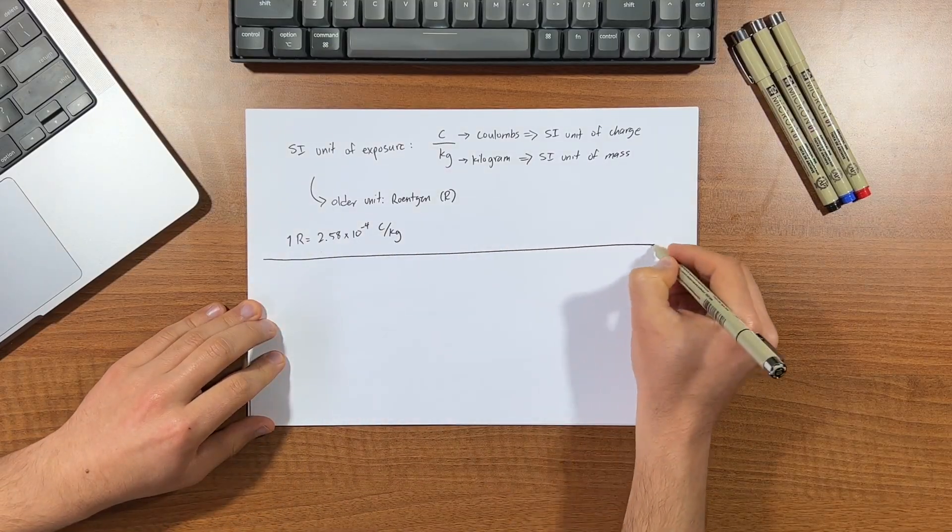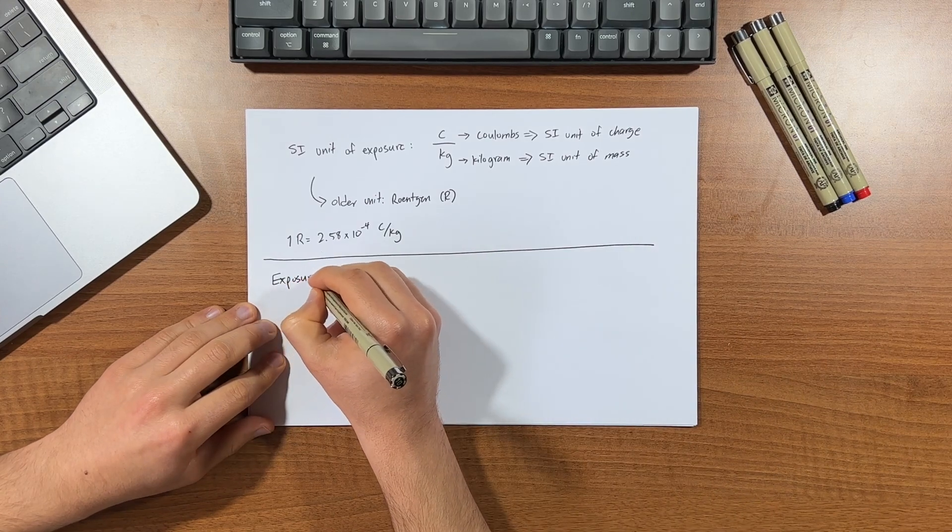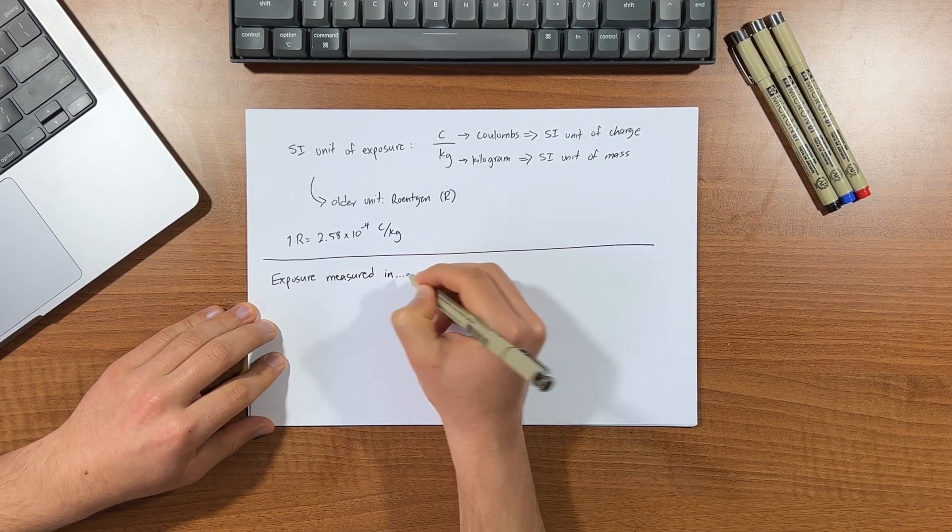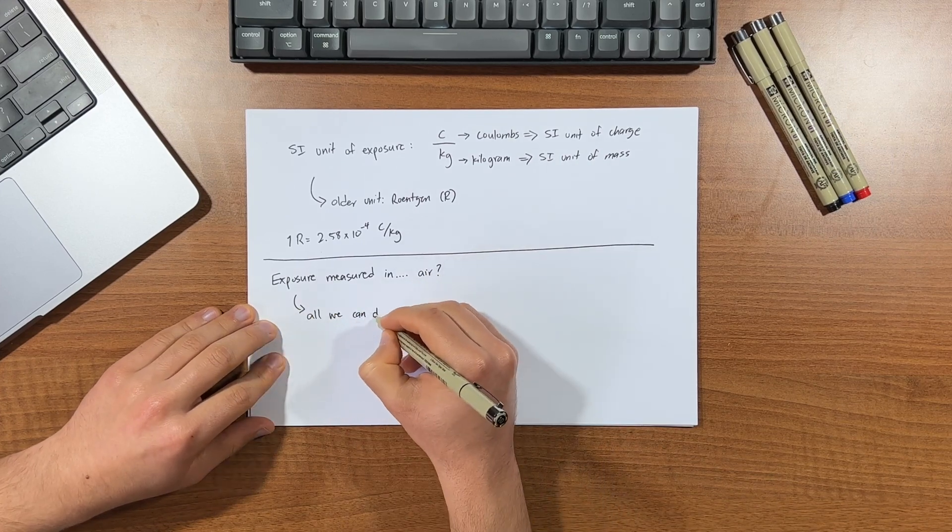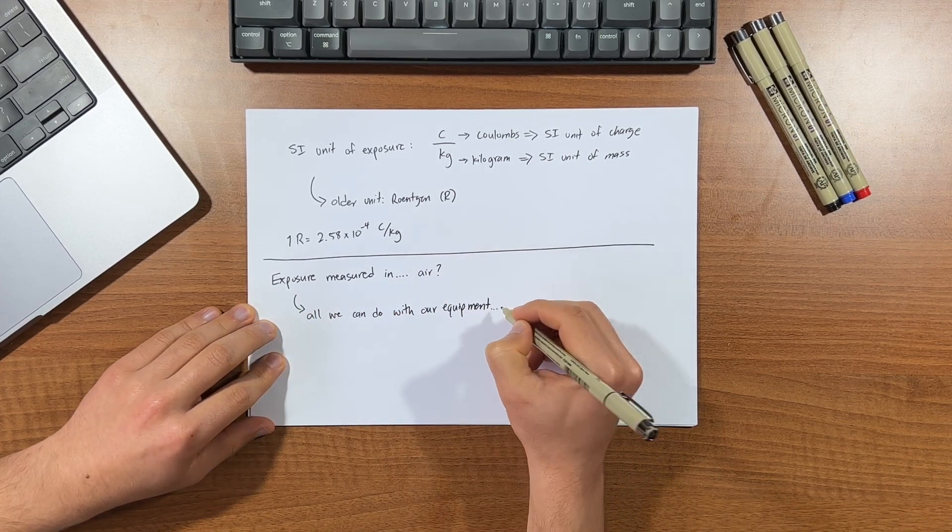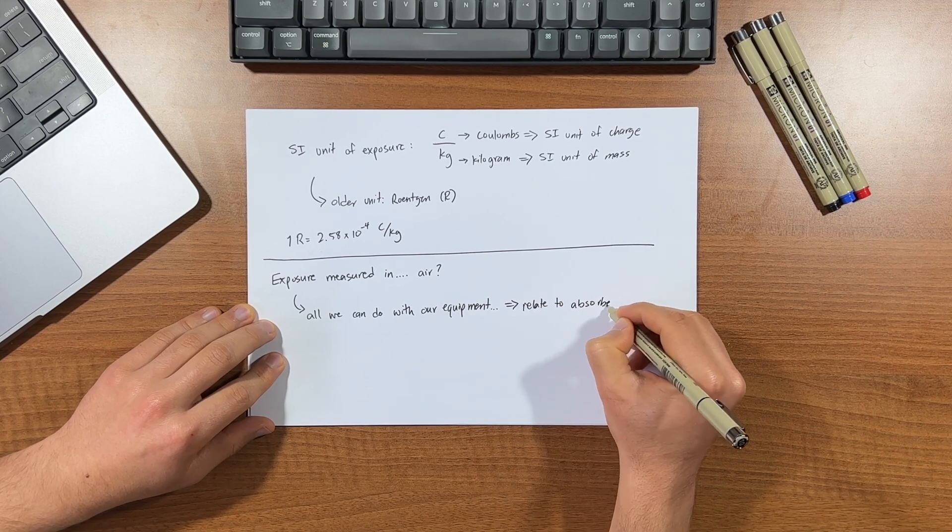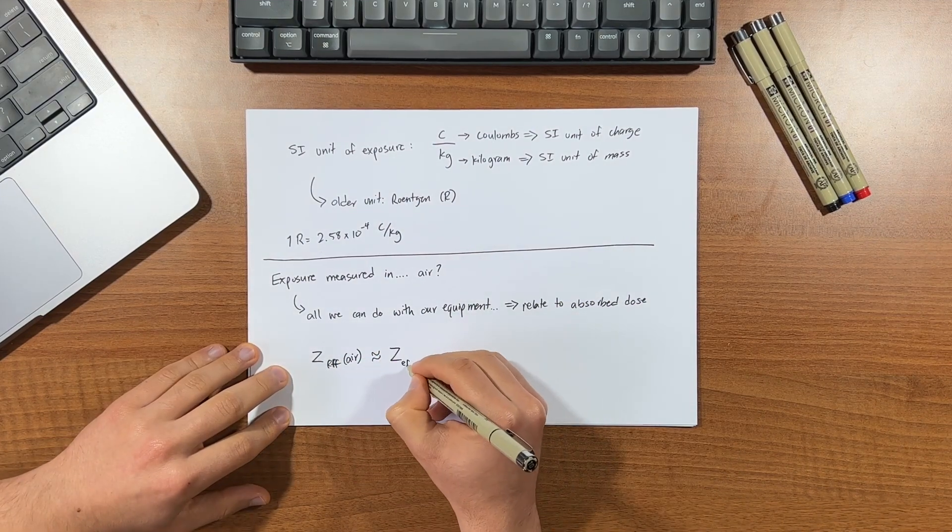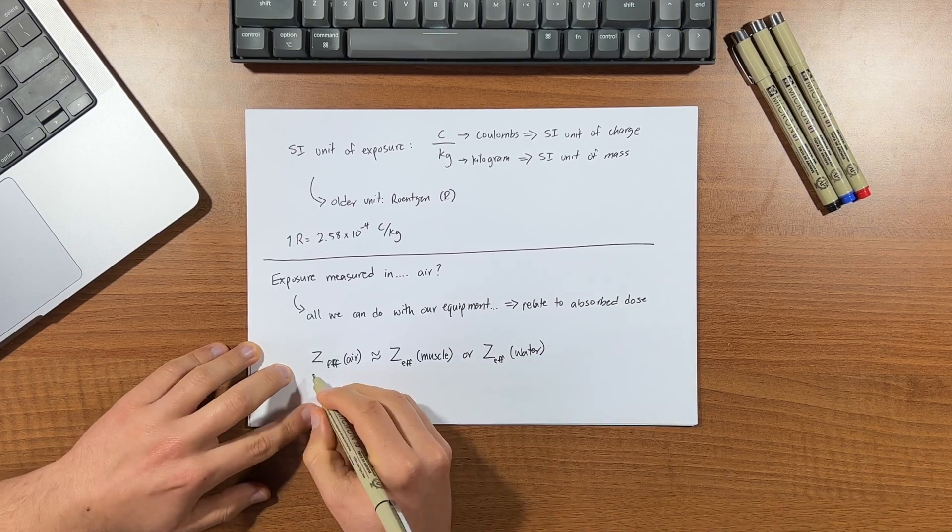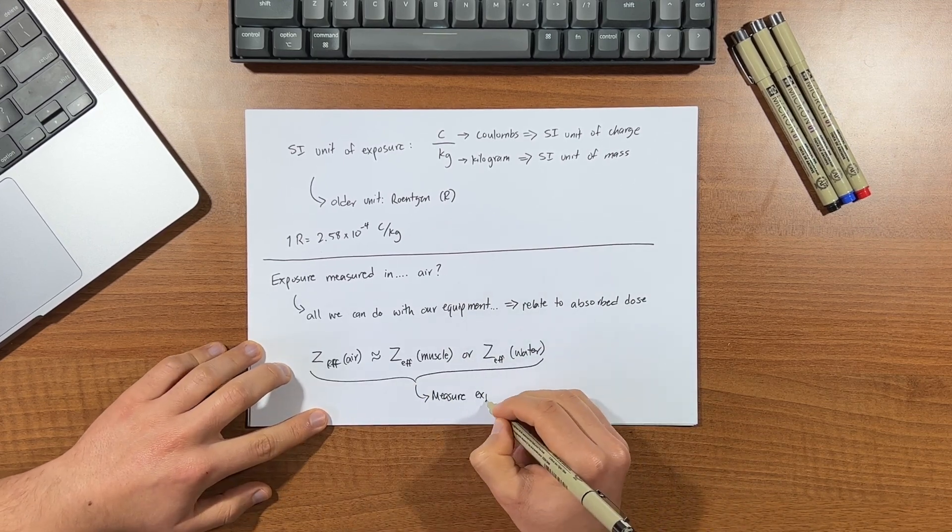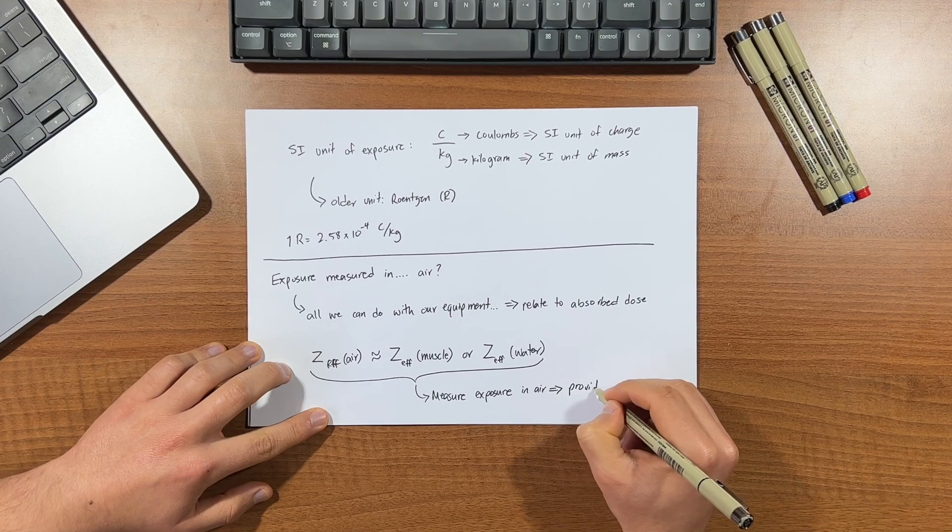I mentioned earlier that radiation dose is measured in a specific volume of air. But why air? Why not measure exposure directly interacting with human tissue? Well, it's a limitation of our equipment, as it can only really measure exposure in air, which we then take and relate to absorbed dose. Now, interestingly, the effective atomic number of air actually closely matches that of muscle and water. And it's this similarity that allows us to perform dosimetric experiments and measurements in air, providing insights into what occurs in the human body.